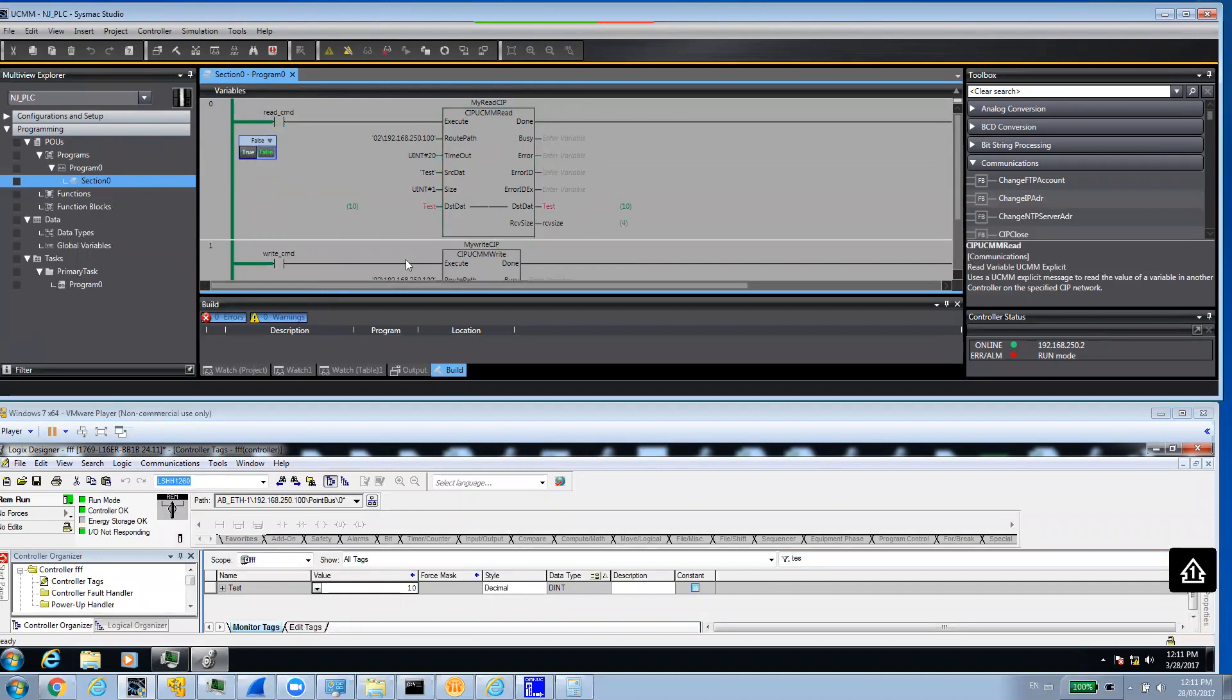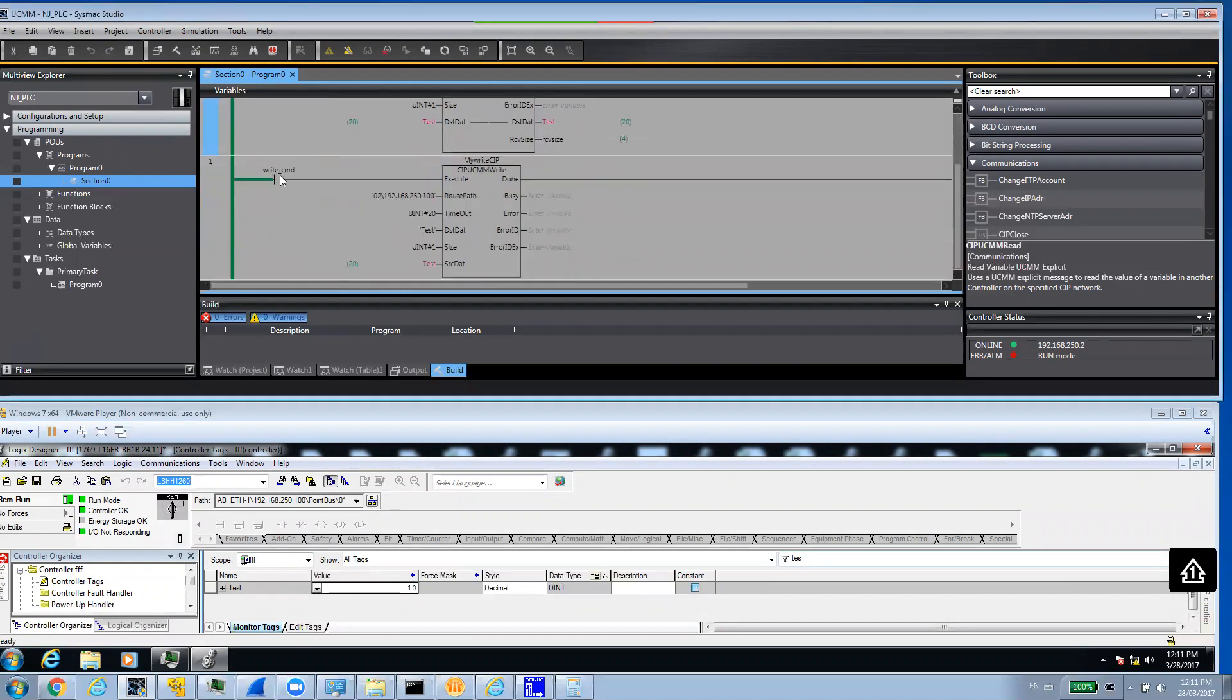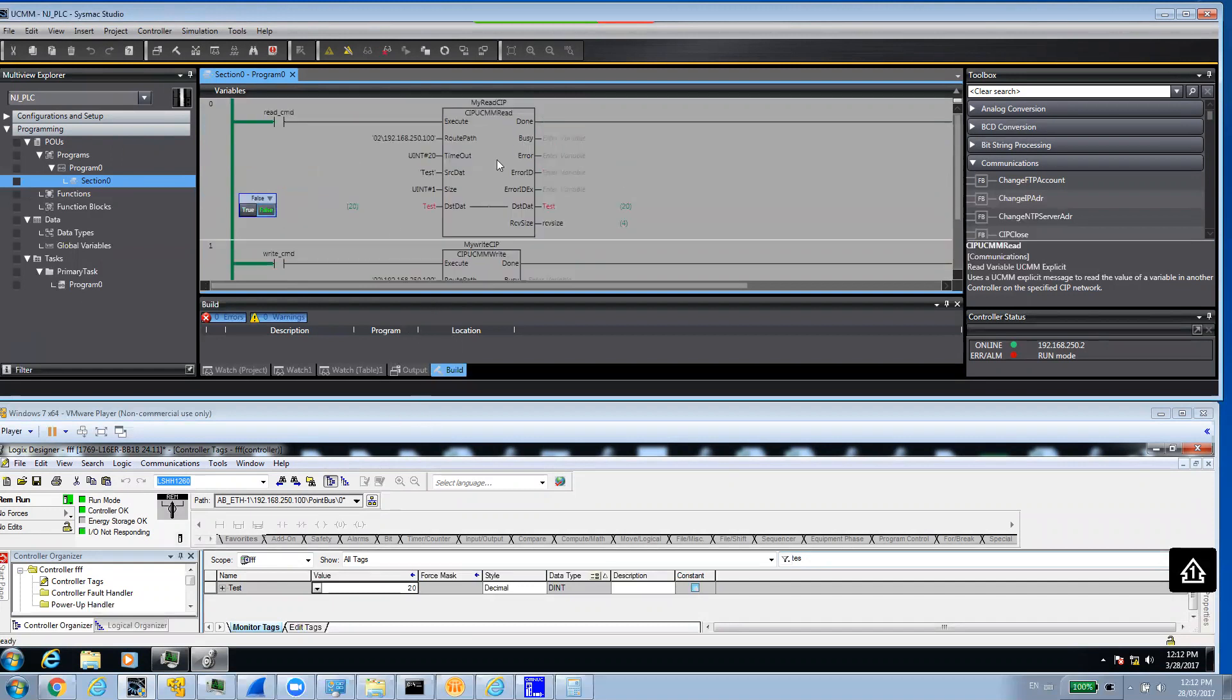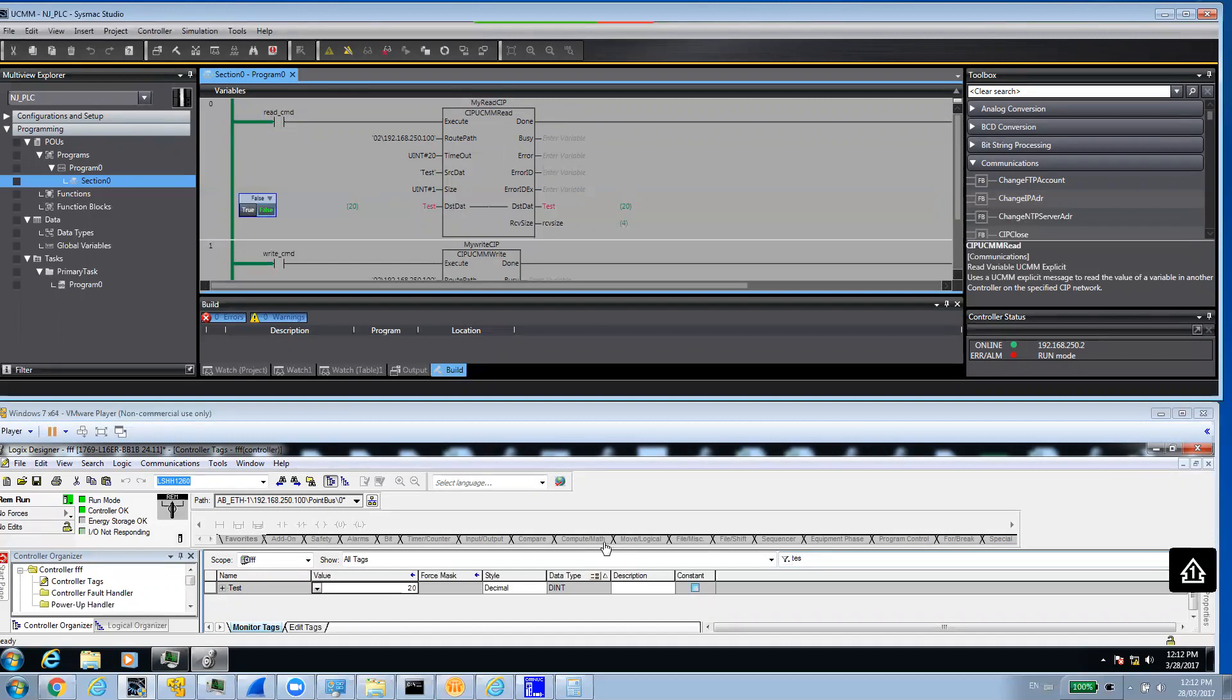Now, I'm going to see if we can write to it. I'm going to change the value here to say 20. And in the same way, I'm going to initiate the command for writing. Say true. And we can see here instantaneously has changed to 20. That's simply how you can basically read and write a variable from an NJ PLC to a third party PLC over EIP using explicit messaging. In this case, it's Compact Logix.